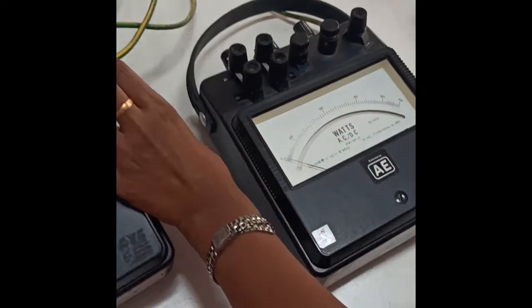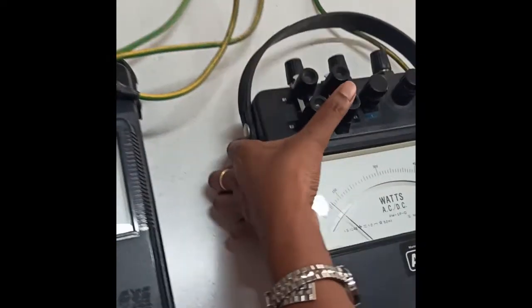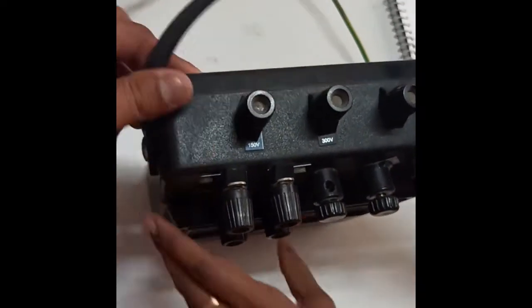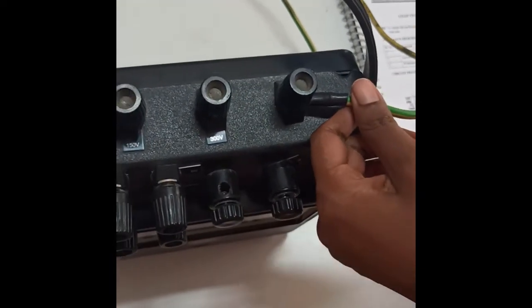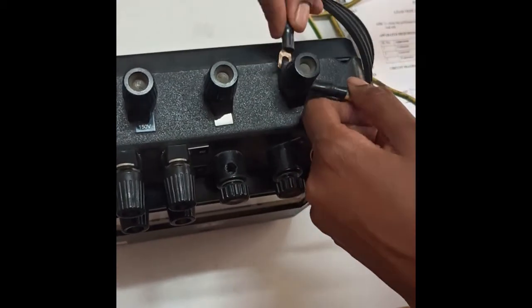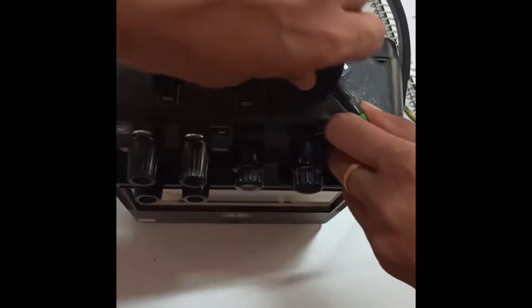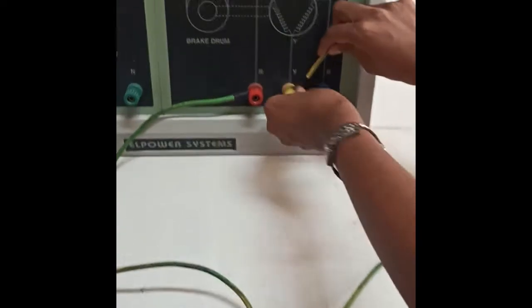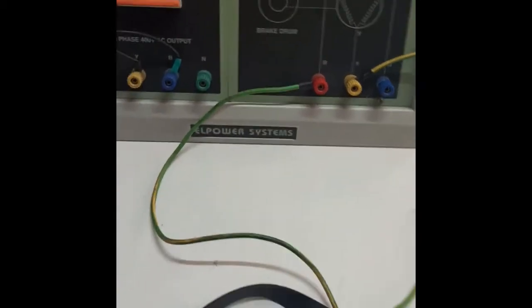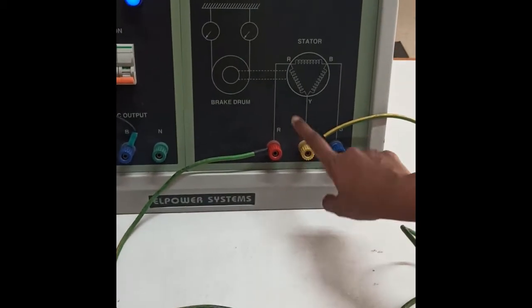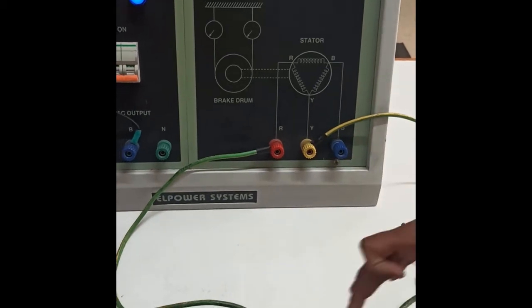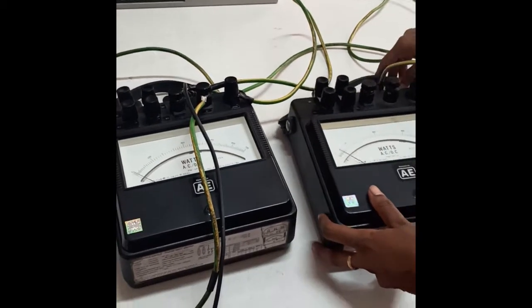Now from the same point, as you can see in the circuit diagram, both V terminals of W1 and W2 have to be shorted. So from that V terminal, 600 volts, I am bringing it to the 600 volt voltage terminal of W2. And from the same point, another connection has to be taken and given to the Y terminal in the panel, that is nothing but the stator winding. So basically the auto transformer output terminal Y, the machine terminal Y and the V terminal of both W1 and W2 will be shorted. The next is B phase.